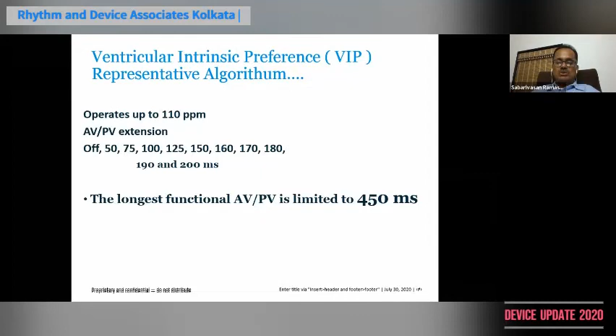So if you see, there is a paced AV delay and a sensed AV delay, which are the optimized paced AV delay and sensed AV delay, whichever you feel is ideal for this patient. And now we bring in the ventricular intrinsic preference, where you have an extension. So you add 200 milliseconds to it, so that you will get an extension now and then. Let's take paced AV delay 200 plus 200: every 1 minute, for one cycle, it will increase the paced AV delay from 200 to 400 milliseconds and look for intrinsic conduction. If there is any intrinsic coming through, well and good, it stays at 400. If there is no intrinsic for one cycle, it comes back and paces at the programmed 200 milliseconds. The same thing for sensed AV delay: 150 plus 200, 350, it will extend for one cycle after 1 minute.